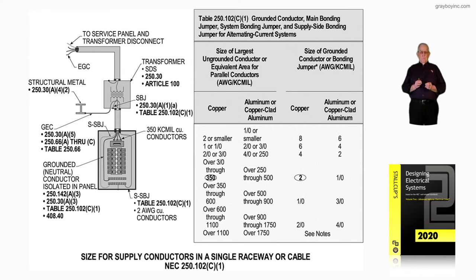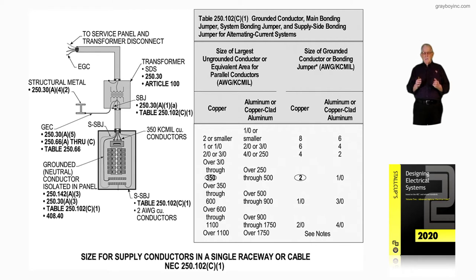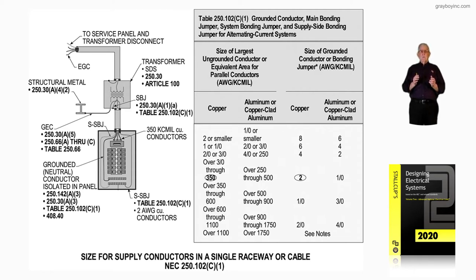Notice here we list the system bonding jumper. Now, if that transformer was located outside and that was service equipment, instead of being identified as a system bonding jumper, it would be identified as a main bonding jumper. But since it's a separately derived system, this system bonding jumper is addressed in 250.30A1(a), and it's sized based upon Table 250.102C1.